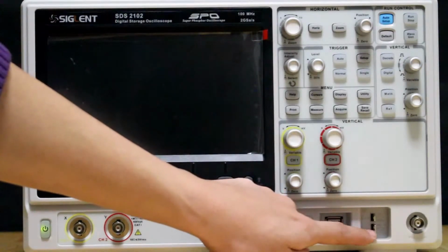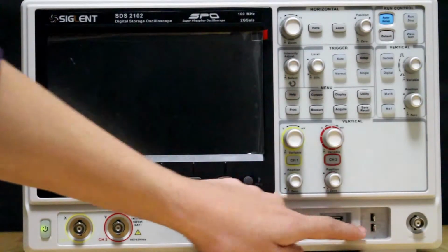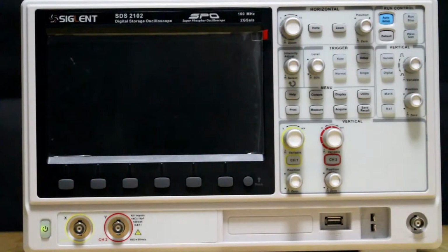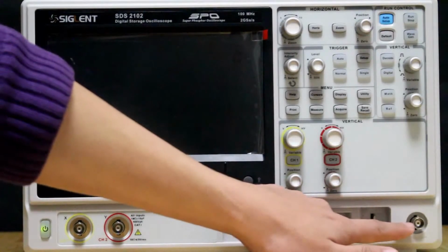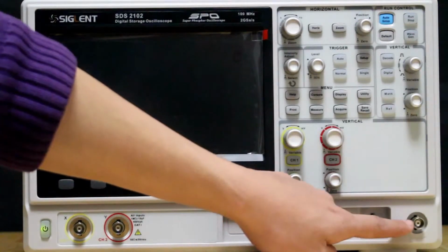And then we have this one, which is for testing the probe settings. It outputs a 1 kHz 3 VPP signal, a pulse signal. And then we have the generator output, which is controlled up there.